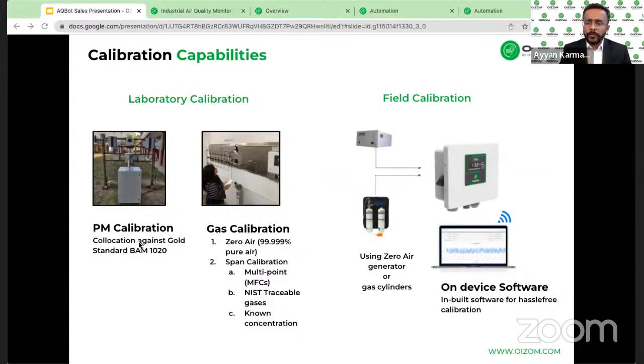But what would you do if you have to calibrate it on site, maybe 6 months or a year down the line? The calibration software has a calibration module that allows you to connect to any smart device, use a zero air cylinder or generator, and then the AQBot can be calibrated without deinstalling the unit from the premises or sending it back to us. You can just take a handy 1-liter cylinder and a smart device and perform the entire calibration there. The on-device data visualization software will help guide you through it.